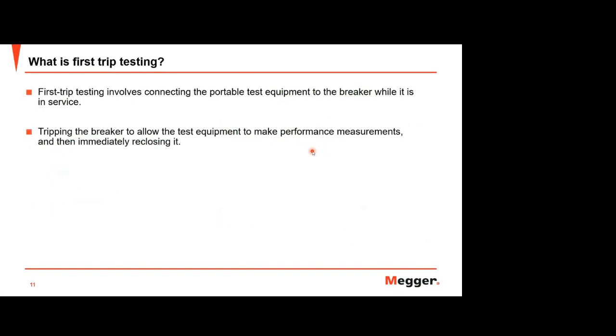Okay, that is the introduction. Now we continue to the main topic. What is the first trip testing? Based on this slide, you can read that first trip testing involves connecting portable test equipment to the breaker while it is in service. So you do testing while the system is still energized. And then you trip the breaker to allow your test equipment to make performance measurements and then immediately reclose it.